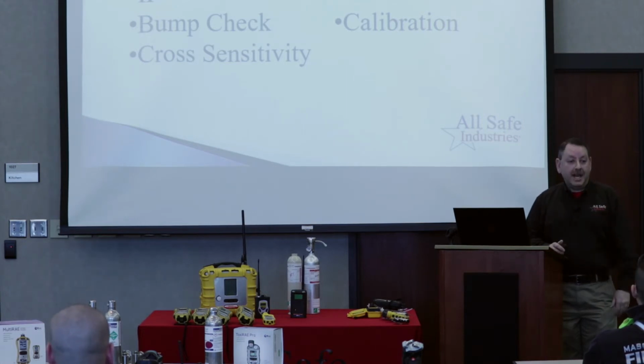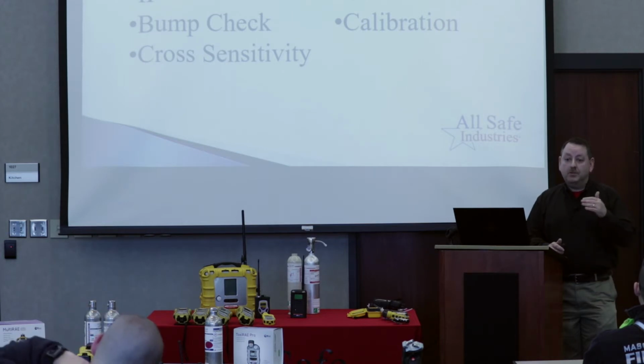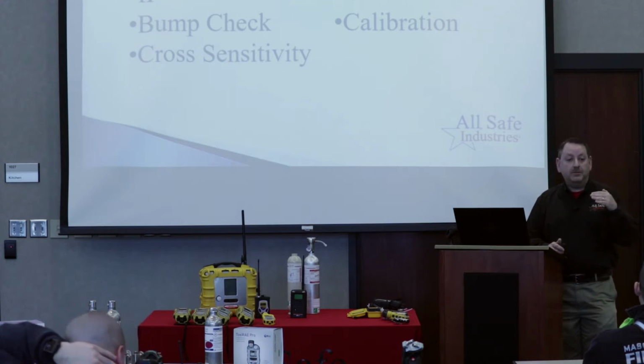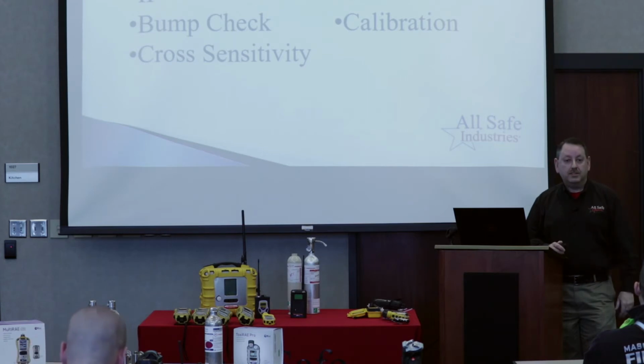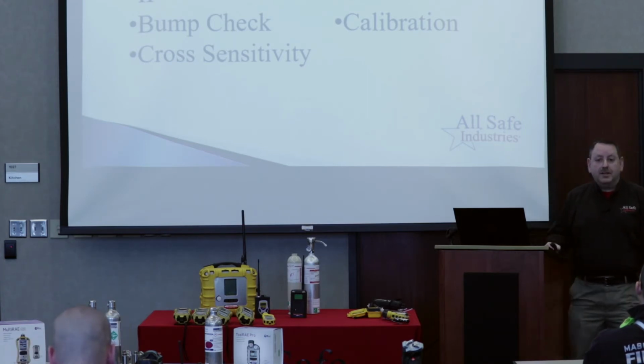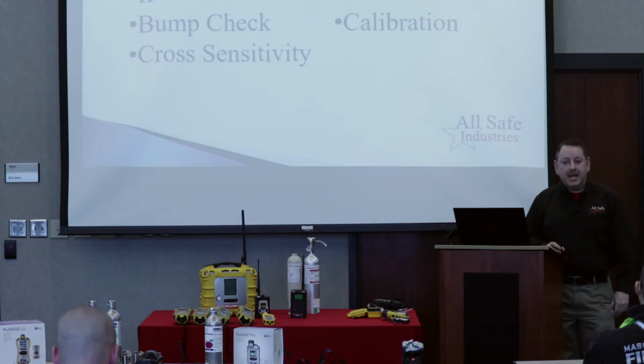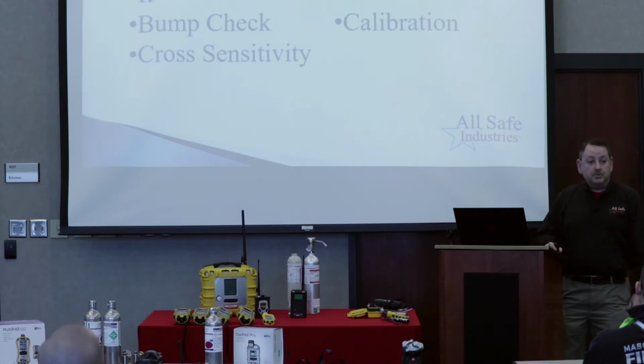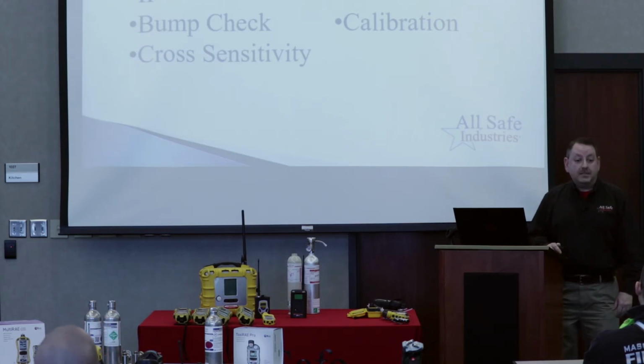We're adjusting the accuracy. So just like the scale in your bathroom, if you want to step on it and get an accurate reading, it needs to start at zero. Okay, the same thing with the calibration gas. We know what value it is, and we tell the sensors to adjust to that. Okay? And then the last term is cross-sensitivity. I like to mention that because some sensors will respond to other gases instead of just the target gas that they are designed to detect.